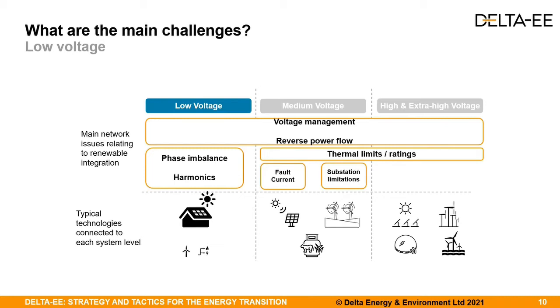Another issue relating to solar PV and low voltage networks is that many installations use single phase inverters, which could result in a disproportionate number of connections on one of the three phases. This may cause phase imbalance in the system, which makes voltage management even more difficult.